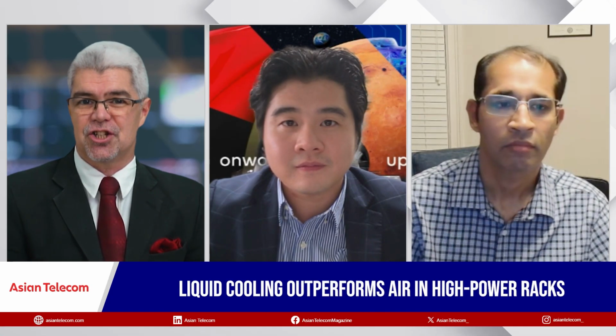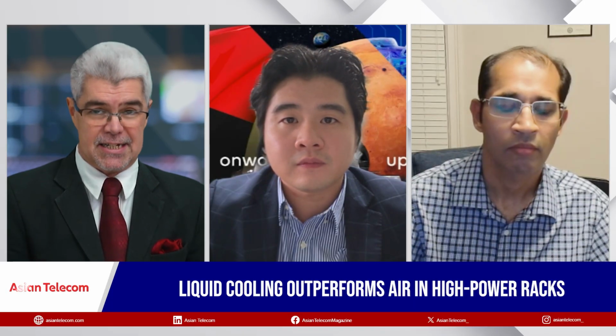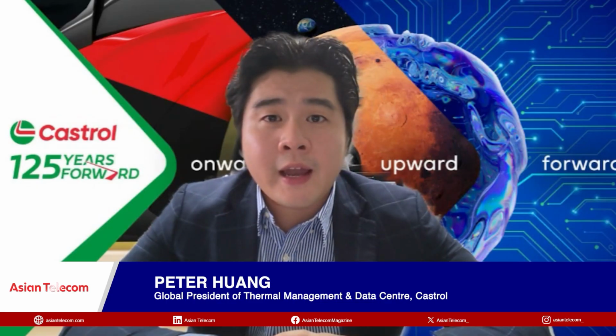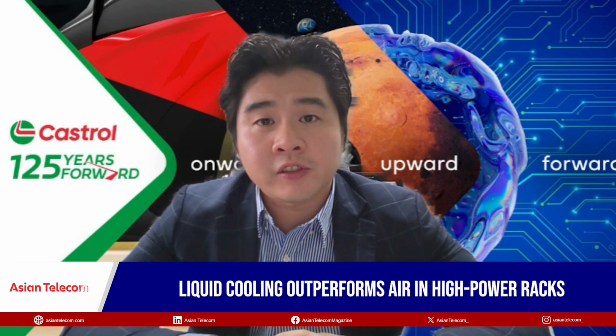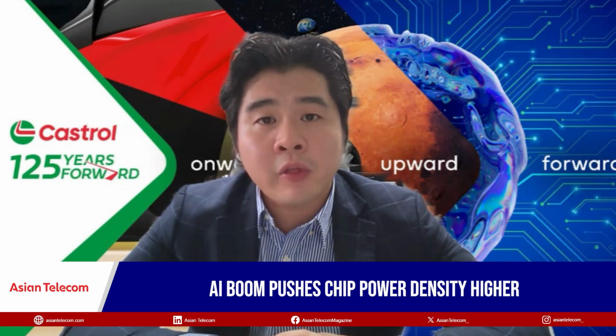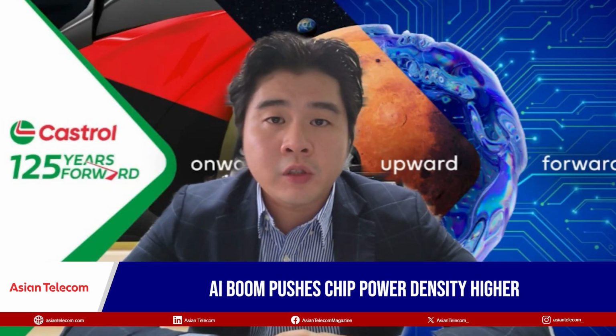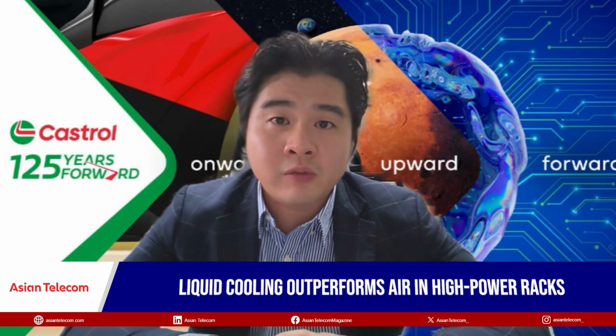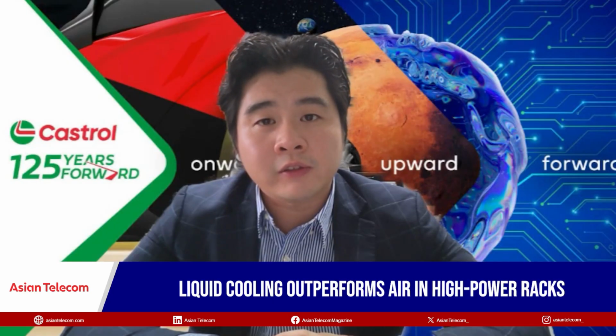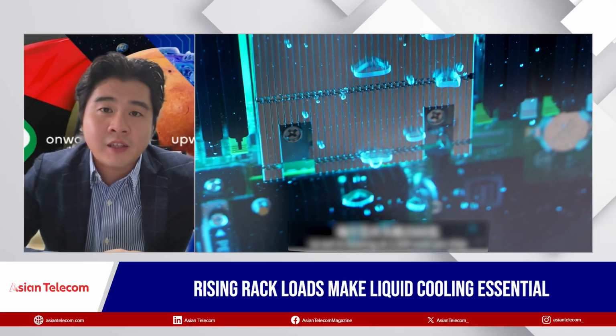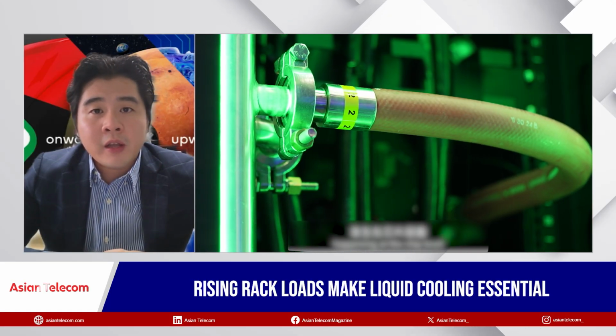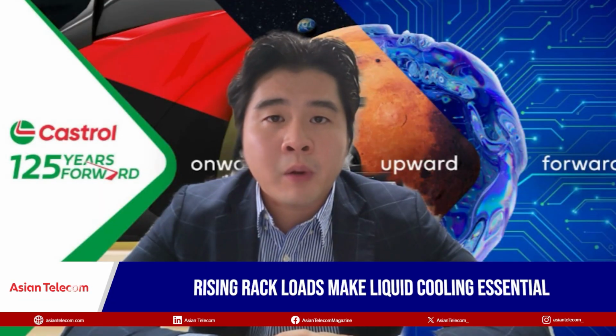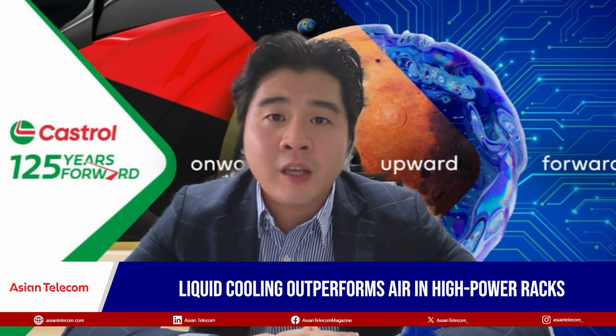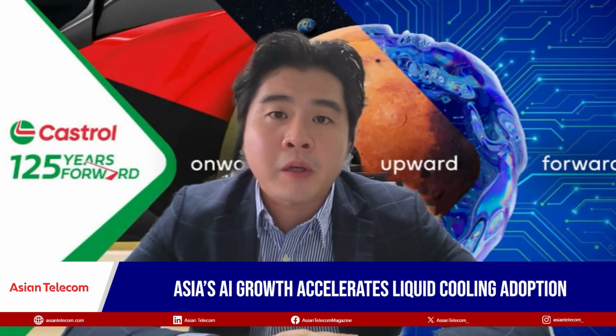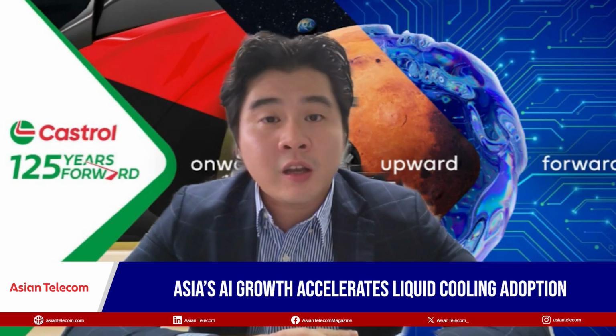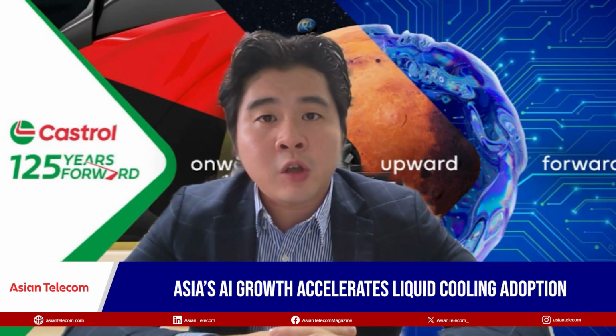How is Asia's digital and AI boom reshaping cooling needs in data centers? AI and the digital boom are definitely changing how liquid cooling and data centers are designed. Per chip, power density is up to 1,000 watts, and we're seeing more of that in the future. Rack density is above 100 kilowatts right now, and we're looking at 150, 200, or even more down the line. With that, liquid cooling is becoming a necessity, the norm, there's no option from it. Maybe there can be a hybrid system, but liquid cooling definitely needs to play a part, since it removes heat directly with higher conductivity compared to traditional air cooling. So it's a necessary thing for AI deployments to go for liquid cooling in Asia.